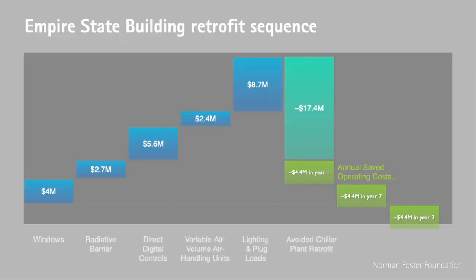And that plus better lights, office equipment, air handlers, and so on, cut the maximum cooling load by a third. But then renovating smaller chillers instead of adding bigger chillers saved $17 million of capital cost, paying for most of the other improvements and cutting the payback to 3 years, or less than 1 year if we had counted non-energy benefits to the owner or the tenants.